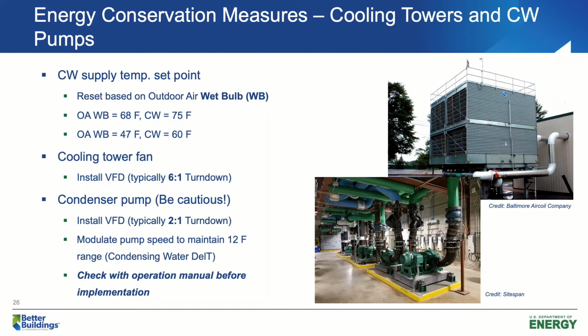Here you can see that we actually increased the approach, the difference between condensing water temperature and the wet bulb temperature. When the wet bulb temperature is 68 degrees, the approach is 7 degrees. But when the wet bulb temperature is 47 degrees, we have increased the approach to 13 degrees. If you have one speed or two speed controls on your cooling tower fans, change them to VFD controls. You will definitely save a lot of fan energy.